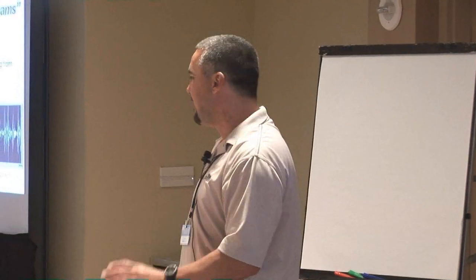And since I've done this presentation, I believe they have taken the step to shut this unit down, open it up and inspect it, because it's a brand new unit. And what Mick told me, I don't know the results of the inspection yet because it's very recently, but the concrete foundation below, I guess there was a steam line and it had caused the concrete pad to buckle, forcing the unit up. So certainly that would have caused a failure, but once again, using these tools, you can see the amplitude changes and the timing changes. And I just put the two recordings side by side here. In my world, comparisons are everything.